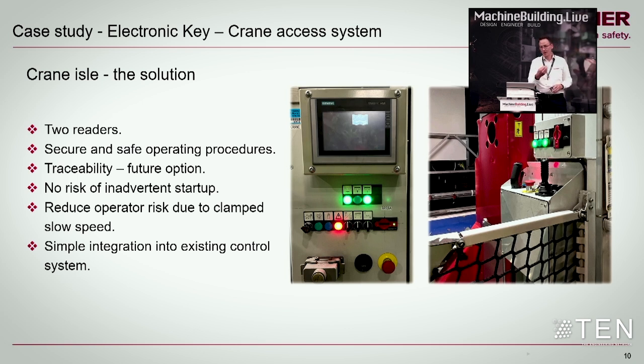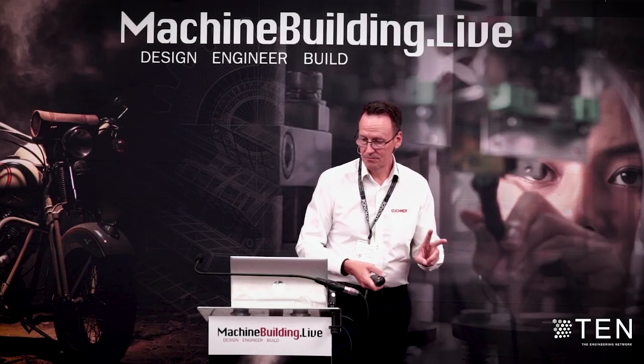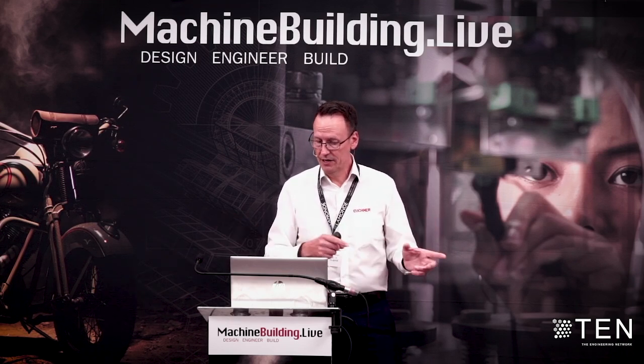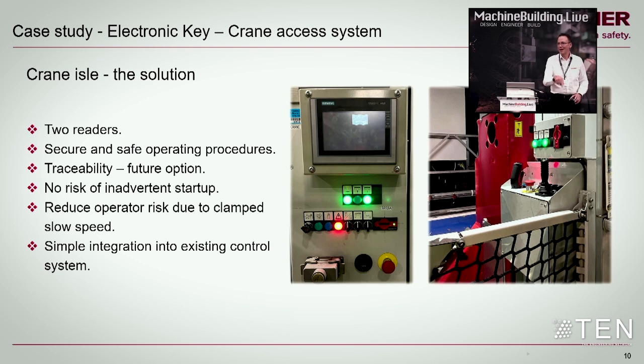If I need to go in and lift things out of the way, that's when I transfer my key to the main control station, and that stops any of the crane local movements. That disables that function. So we've got two readers. It's safe and secure because there's operating procedures in place. The automation layer knows where that key is, so it's traceable. There's no risk of inadvertent startup. So to get the whole system to start at full speed, I need that key in the main reader, which is outside of the cell. Okay, so it will not start.